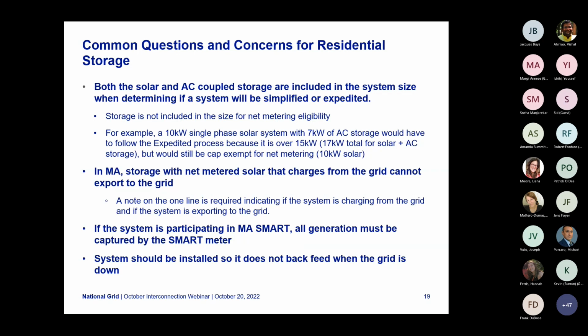Common questions and concerns for residential storage: both solar and AC-coupled storage are included in the system size when determining if a system will be simplified or expedited. The storage is not included in the size for net metering eligibility. For example, a 10 kW single-phase system with 7 kW AC storage would follow the expedited process because the total kW AC size is 17, but it would still fall under net metering eligibility because the inverter is 10 kW.